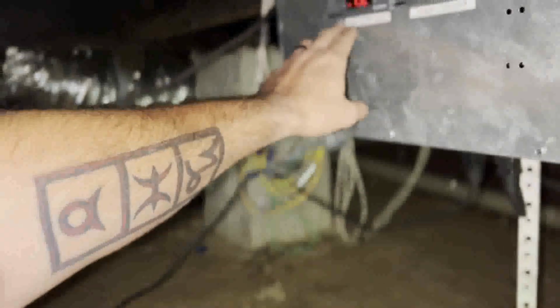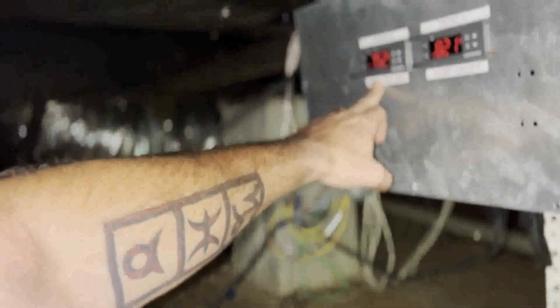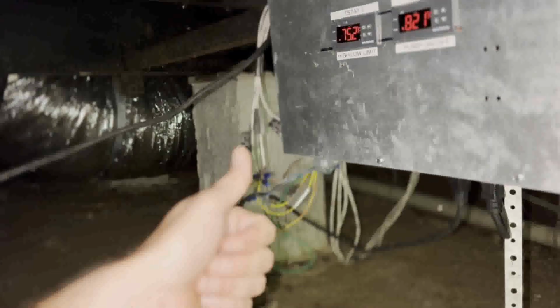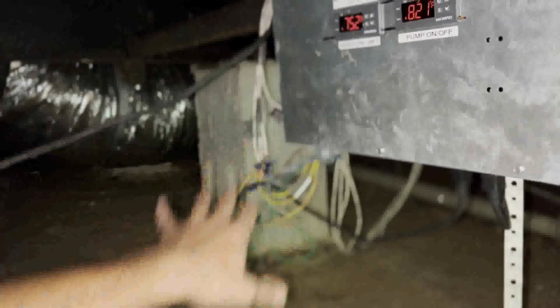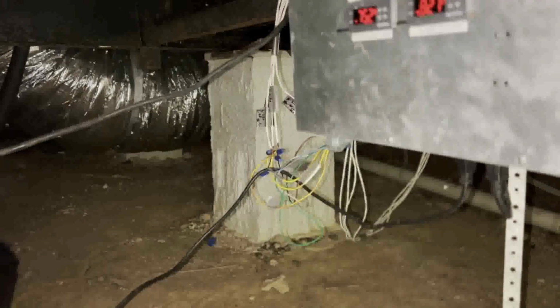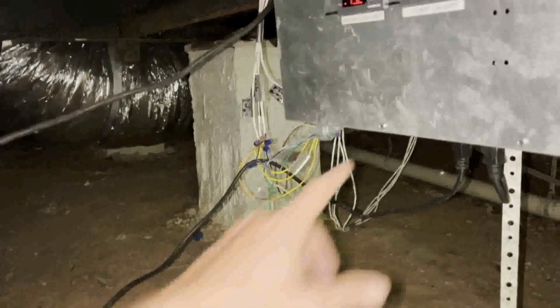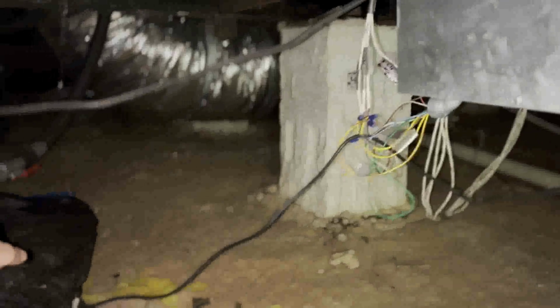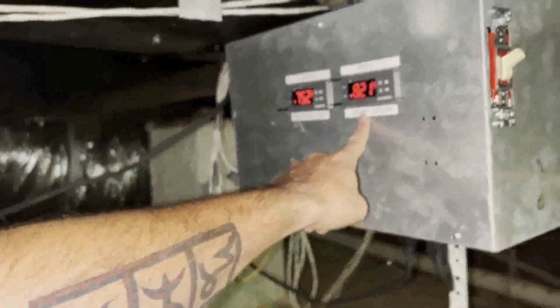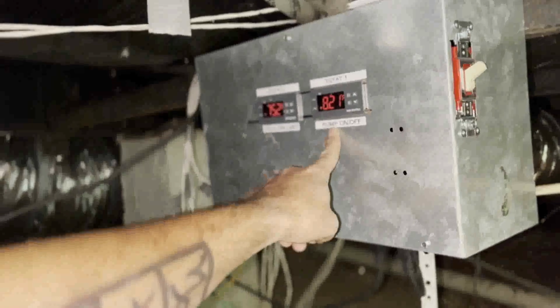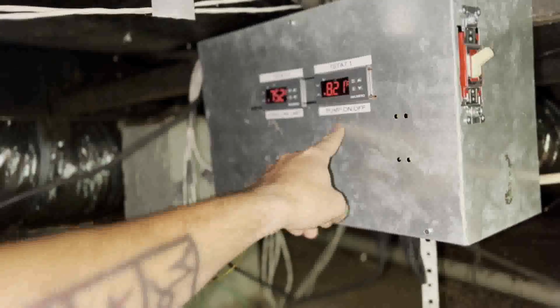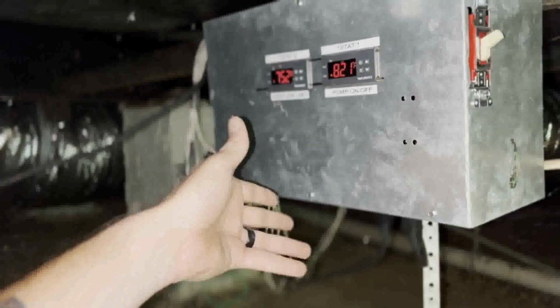That's to turn on the heat in the event that the water gets too hot, and just dump heat into the house. It'll get your attention. Or if the water gets too cold, okay, someone's taking a shower and the heat's running. That's to protect the boiler, to control the return water temperature. This is just to tell the pump, turn on, your water's hot enough to actually do something with, or turn off, your water's not hot enough to do something with. So that's the skinny on that.